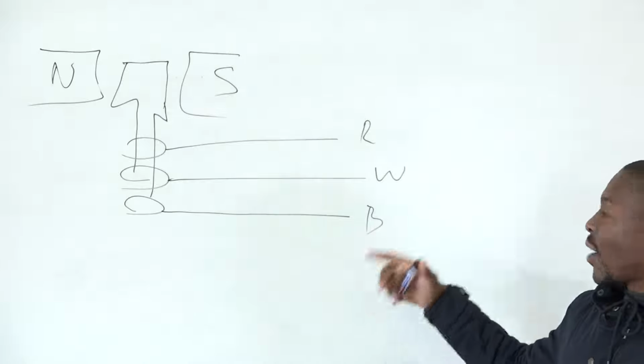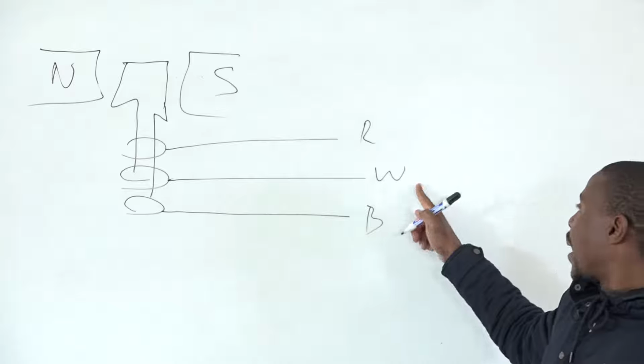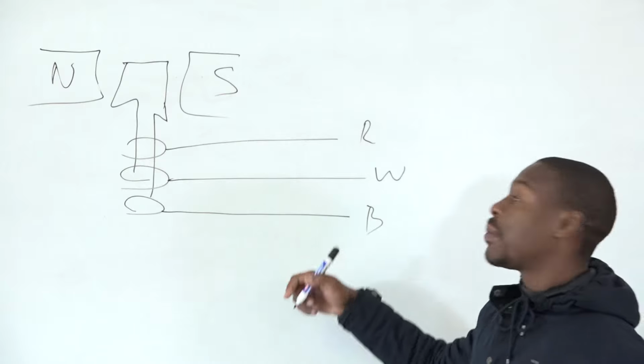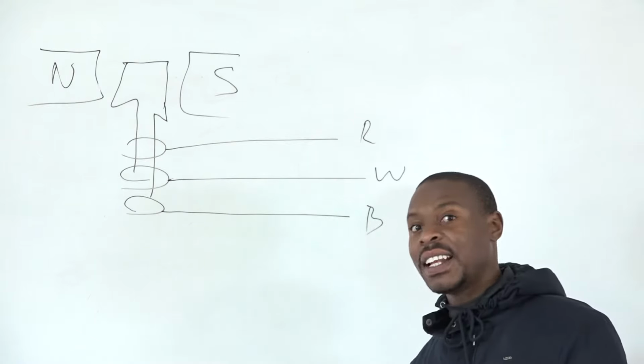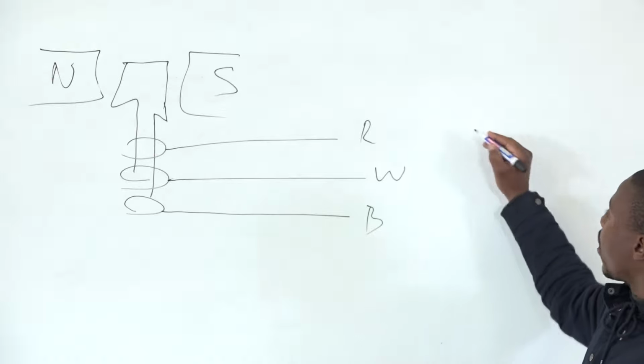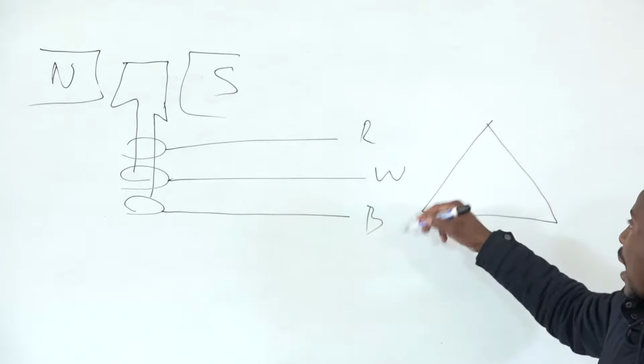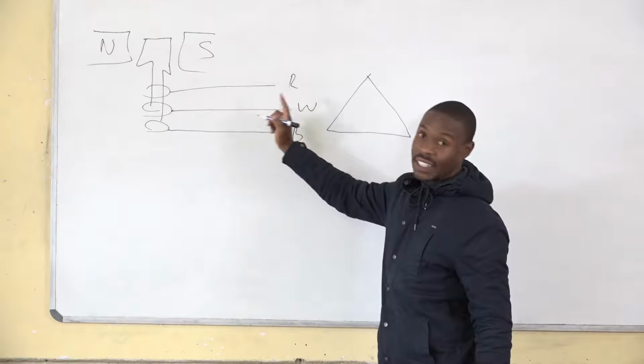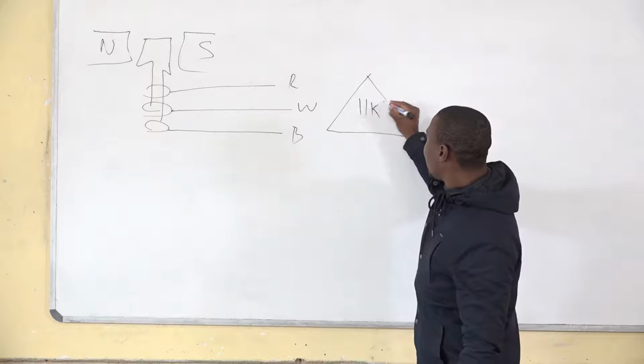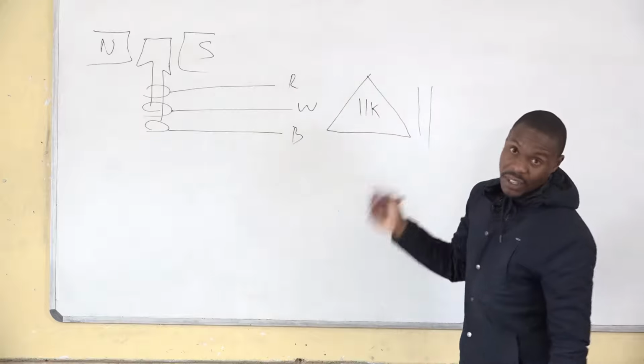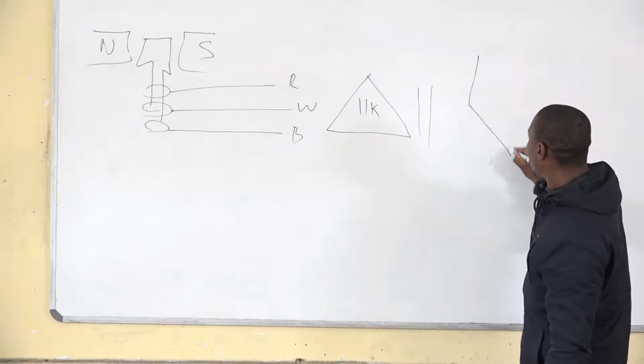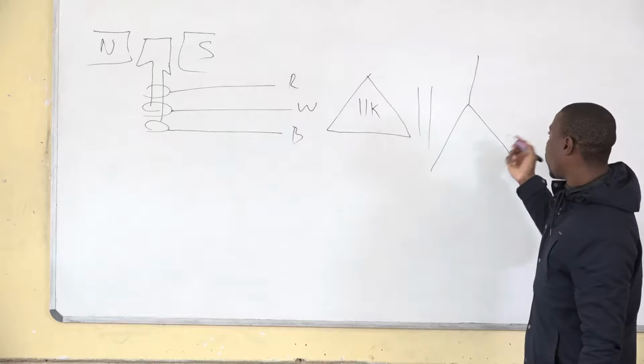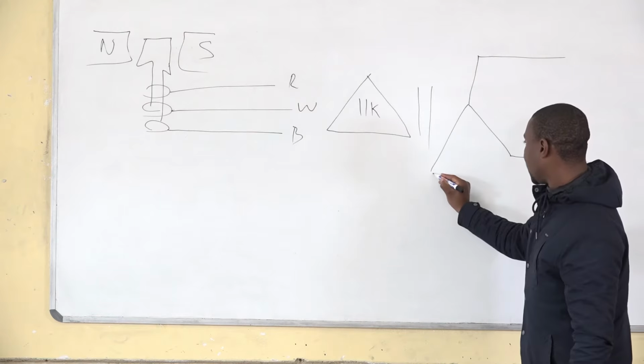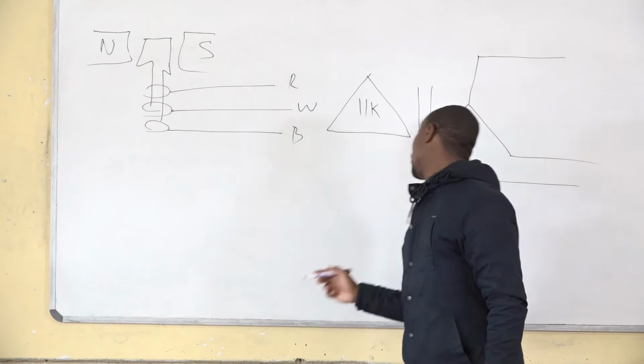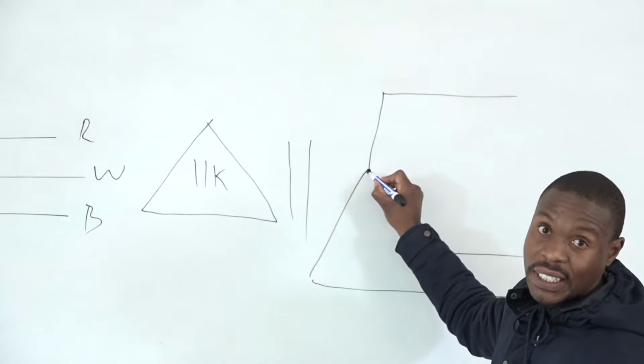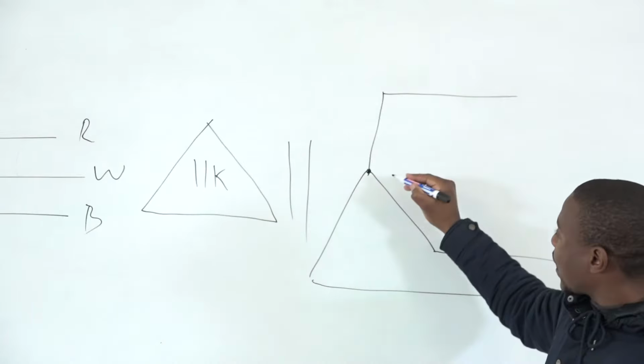Okay, from this side, I won't touch it because it's on another level. These three phases coming from the slip rings go straight to a transformer, which is configured in delta. So our primary side of the transformer will be configured in delta. Let's say the alternator has given us 11 kV. Then these 3 lines go to the delta. Then our secondary side will have a star point, which will be stepping down the voltage to, let's say, 415 volts. So you will still have 3 lines again, but the only difference is that you now have 4 wires, because this part we call a star point. From the star point, that's where we get our neutral.